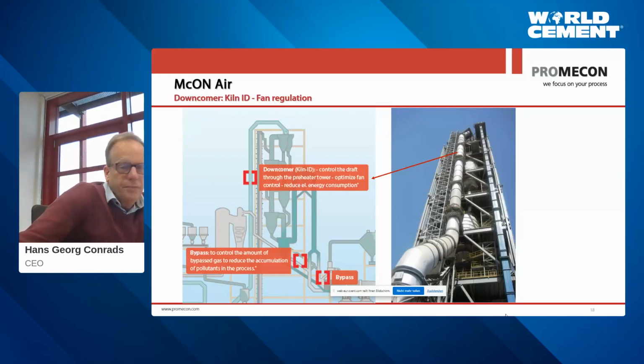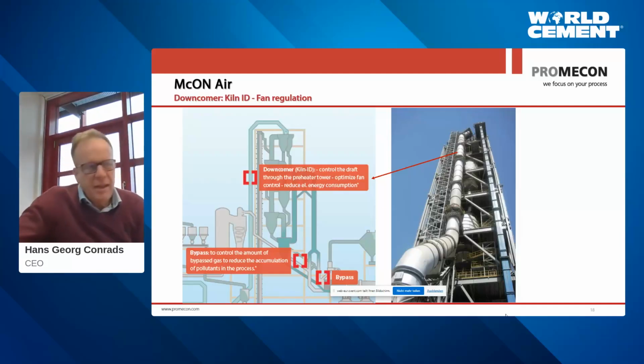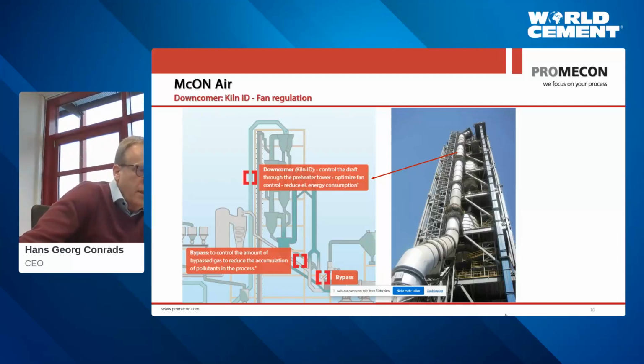and the measurement has a very bad error behavior. So what our customers usually do is they take the O2 measurement as a long-term trend in order to keep the rotary kiln at the right stoichiometry. And they add one measurement on the downcomer that you can see there, the PROMECON measurement, in order to have a short-term fan control that allows them to reduce process noise and have a far better regulation of the total gas flow through the kiln.